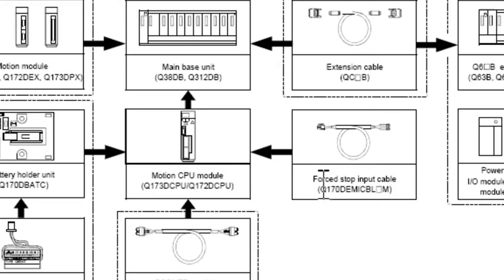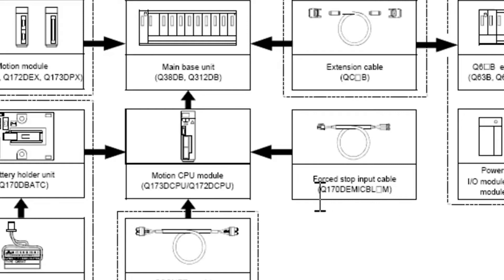You can see here there's a forced stop input cable. You're going to need this cable in order to disable this E7 alarm on the amplifier. This cable is a Q170D EMI CBL dash M.